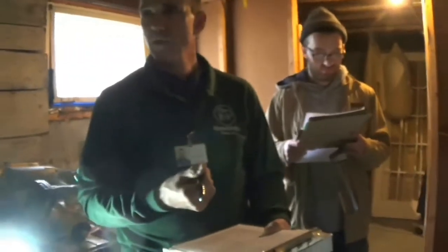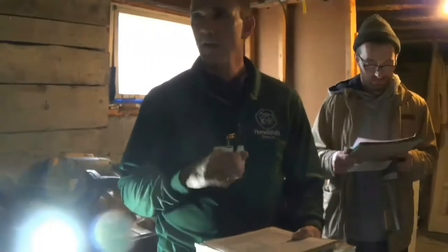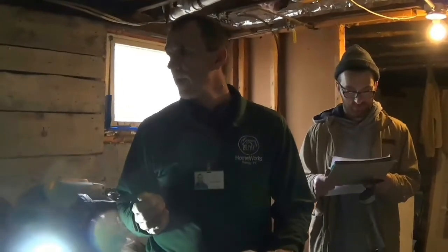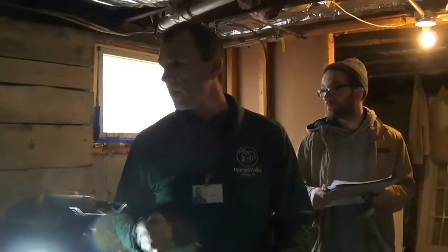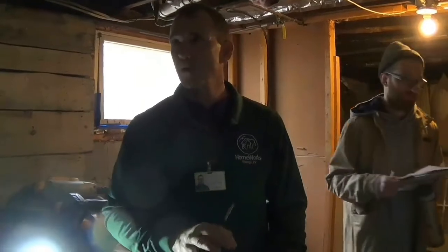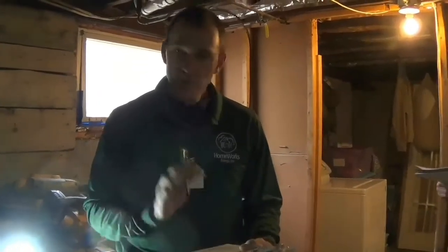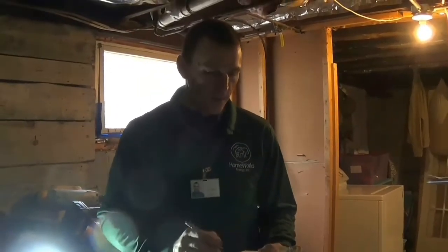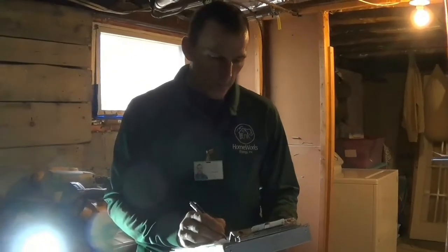I am able to smell the thing they add to natural gas that would tell me if there was a lot of unburned natural gas down here. I don't smell any of that. I do smell a little bit of paint varnish. I would warn the homeowner that it's not safe to have things that are flammable in a combustion appliance zone. But there's no unburned gas. There's not a gas leak going on down here. So I would circle no.